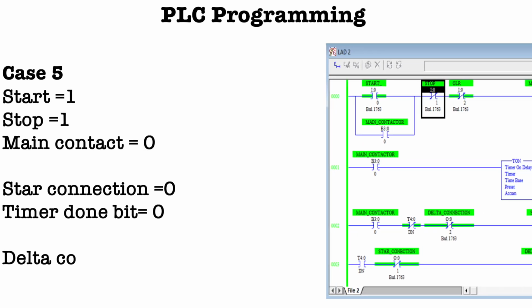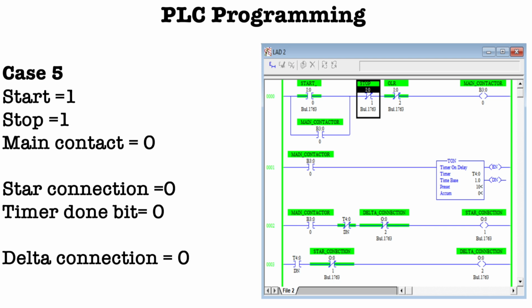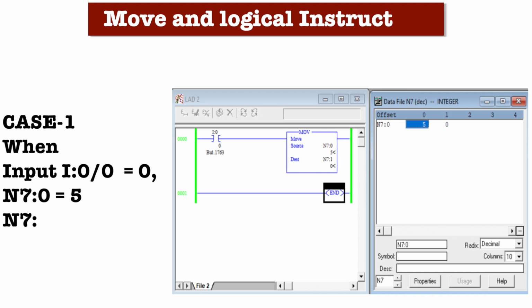Next case, suppose I press the stop switch. It is also similar because the stop switch and OLR switch are connected in series. So when I press the stop button, my main contactor also doesn't get any supply, and because of that my motor will stop, right? So this is the operation of my star delta starter in PLC programming, right? And next we will see the move and the logical instructions.